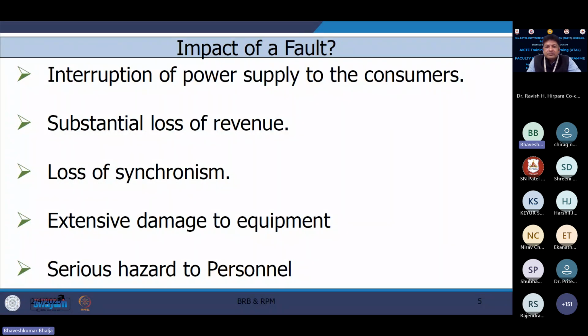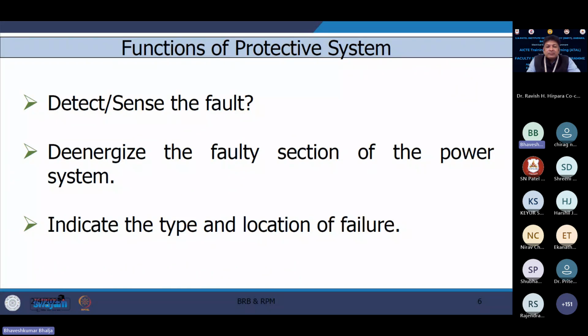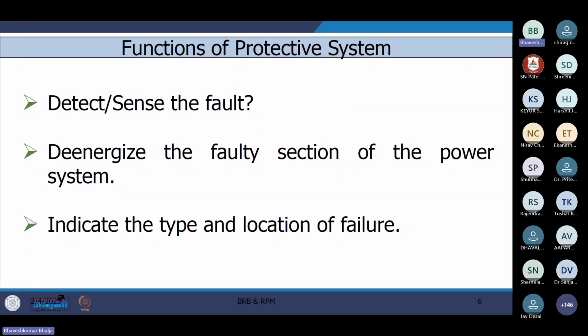We do not bother about this in our country. So if you design any system, the first thing is you have to design a system which is capable of detecting the fault, whether it is anywhere on the system, AC side, DC side, anywhere. Then once it is detected, you have to de-energize the faulty section without affecting the healthy part. And once isolation is done, the last phase of the task comes into the picture: what is the type of fault and at what location the fault has occurred.